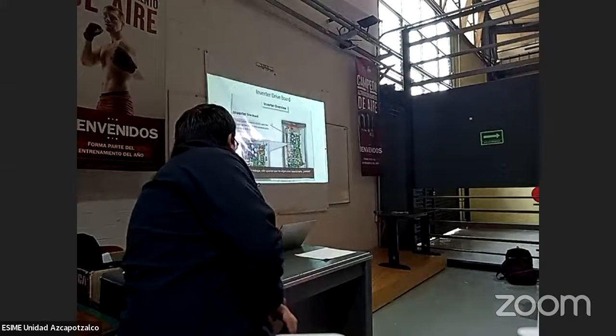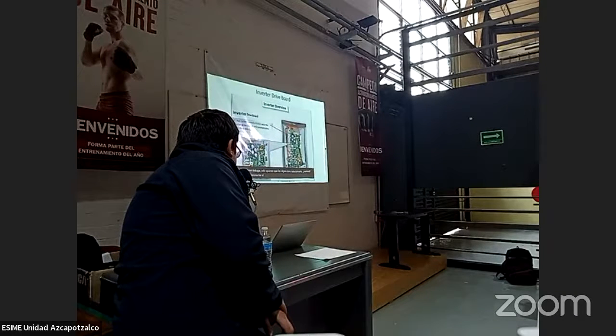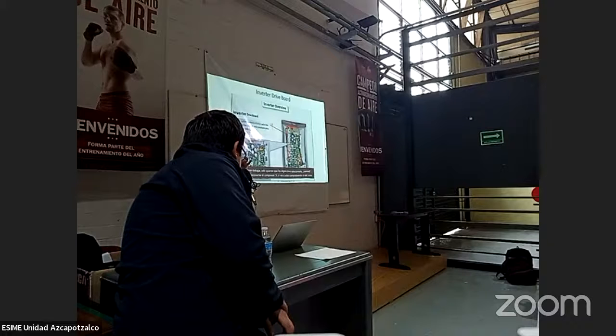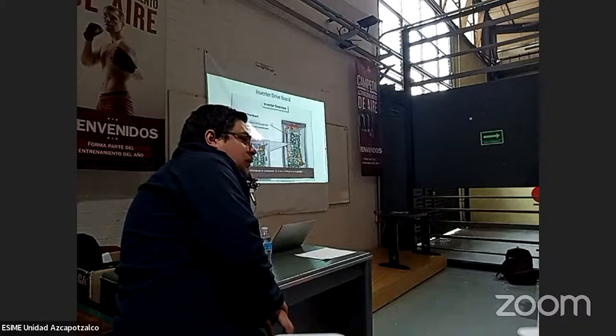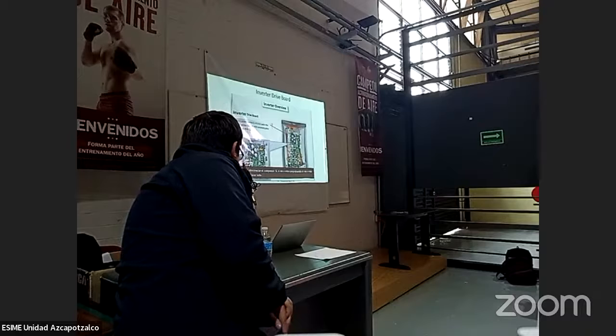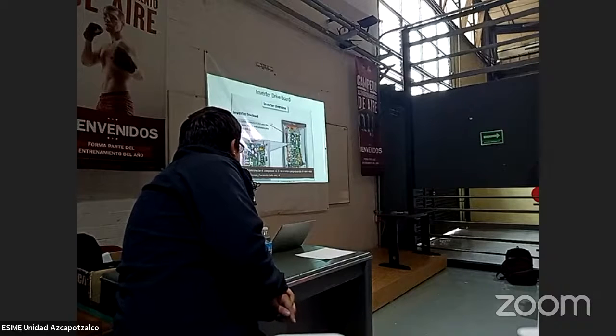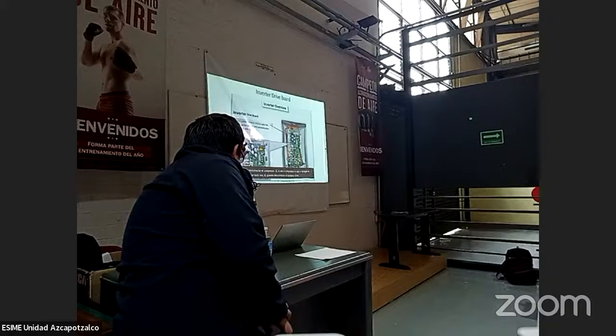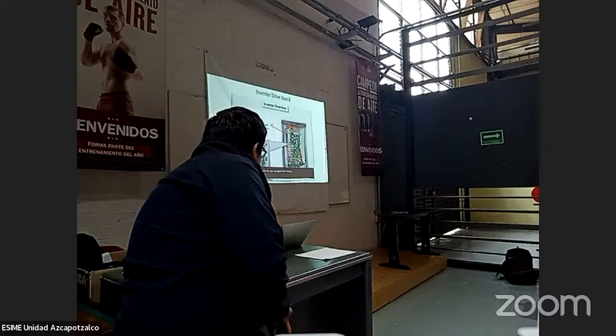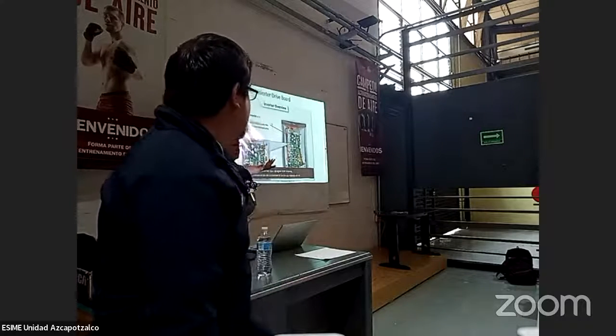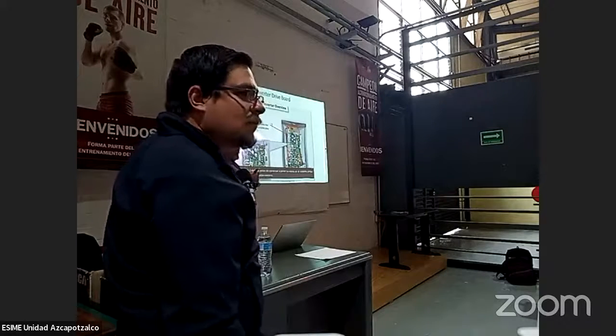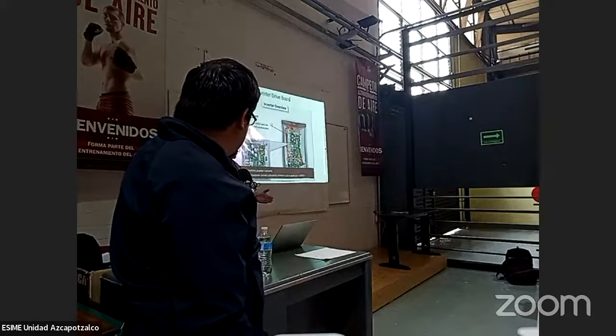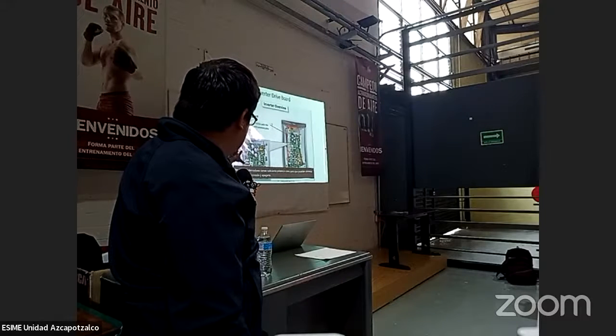Yes. If you're going to be checking, if you're going to be ohming out the compressor, doing all that, yes, you want to disconnect the system, turn the power off, and then check it. Also, anytime you turn power off on this system, give it at least 5 minutes before you start putting your hands in the system, because these capacitors can kill you. These capacitors have enough power that they can go straight to your heart and shut you down. So give it time to dissipate, make sure all lights are off the board, then you start troubleshooting, okay?